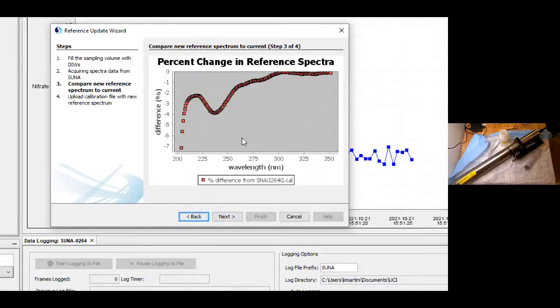And then what I do, I want to compare my change in reference spectra. I'm going to tell you that I have not updated this reference spectra in a couple of years, but this is actually doing pretty well. There's a couple of things you do want to look for here. You want to make sure that this is a smooth, continuous line and you don't have any breaks. So that's where we're doing good here. And we also want to make sure that in this wavelength range from about 217 to 240, you're not seeing anything larger than 10%. If you do see something larger than 10%, that might be indicating that you should update your reference spectrum, but this looks pretty good.